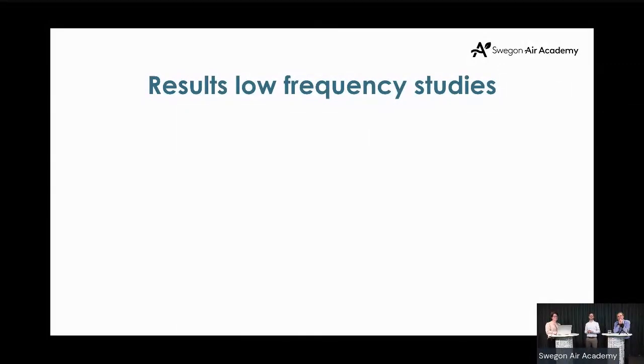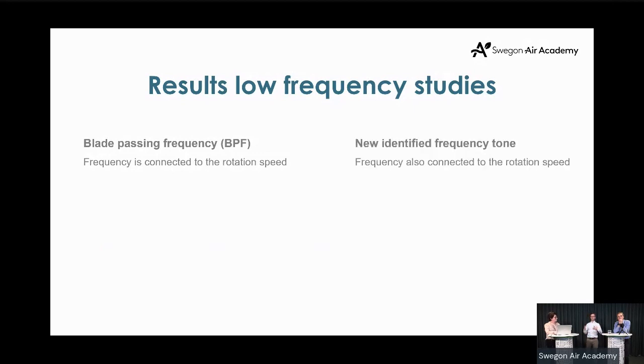To sum up these studies, the blade passing frequency is connected to the rotation speed, as we said, but this new infrasound frequency tone is also connected to the rotation frequency. And here we have the equations for them. In my study, I used 2,800 RPM. If we calculate the frequencies, the blade pass frequency is at 327 hertz, and the infrasound is at 2.4 hertz. And this is extremely low. We couldn't measure it with a microphone. We had to measure it with vibration meters. And if we calculate the wavelength, it will be 1.5 meters for the blade pass and 133 meters for the infrasound. Building an attenuator for 133 meters would be impossible.